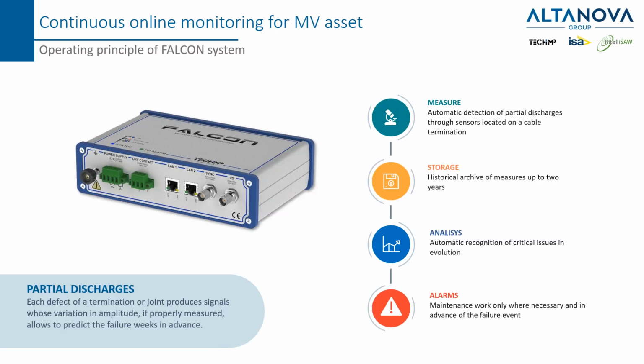Actually, this unit has the benefit that it is fully automatic. The measurement of the partial discharge is done through the sensor located on a cable termination, basically. The storage is inside the unit and can hold up to 2 years of data. The analysis of the unit is completely automatic and can recognize the critical issue and its evolution. The alarms are provided through standard communication tools like the other system they introduced, but in a later part we will go into more detail.